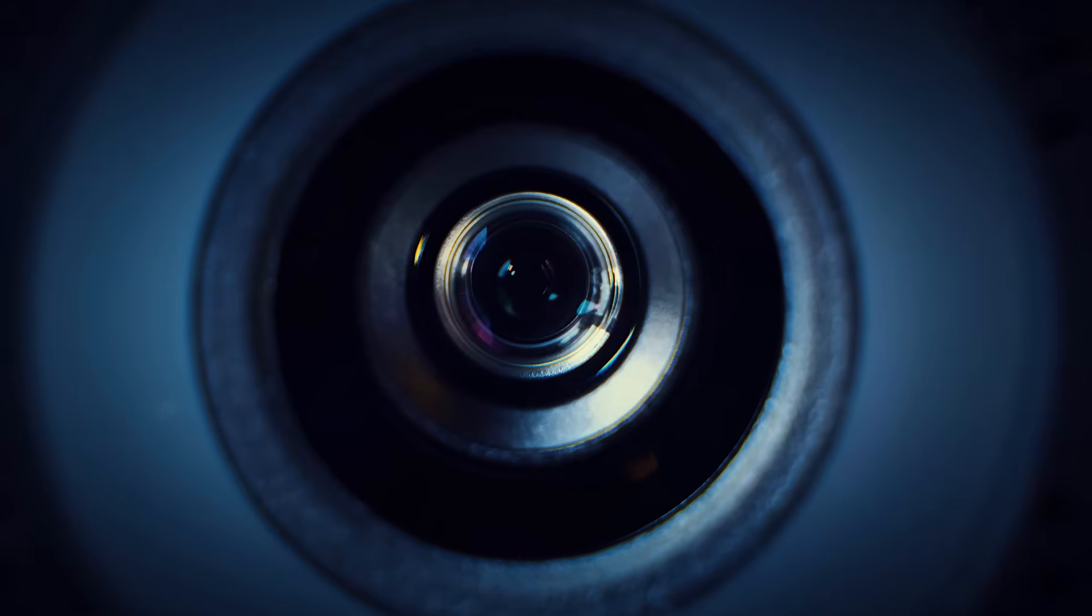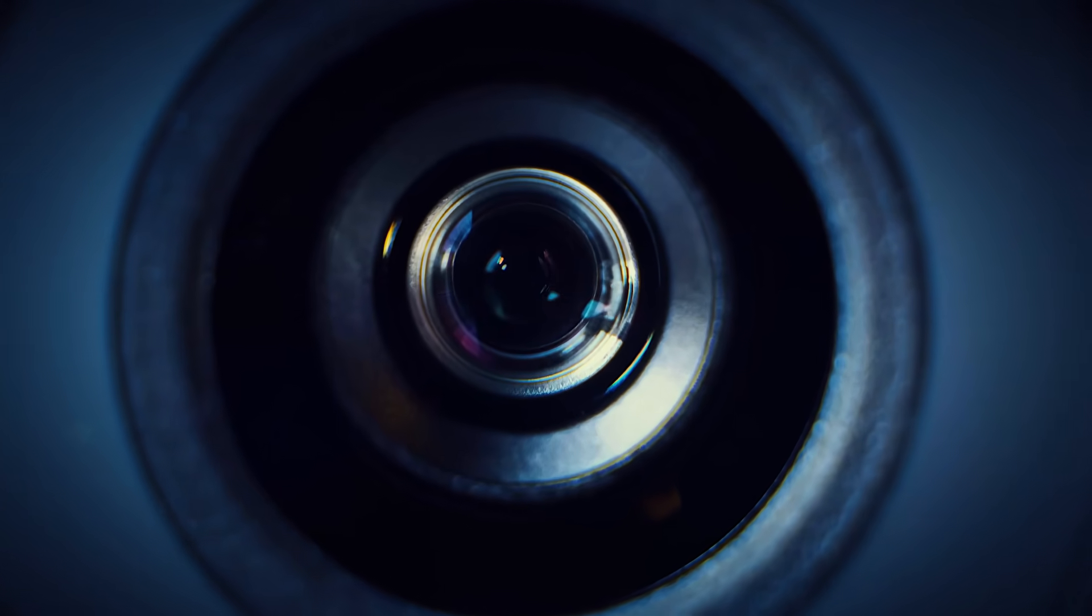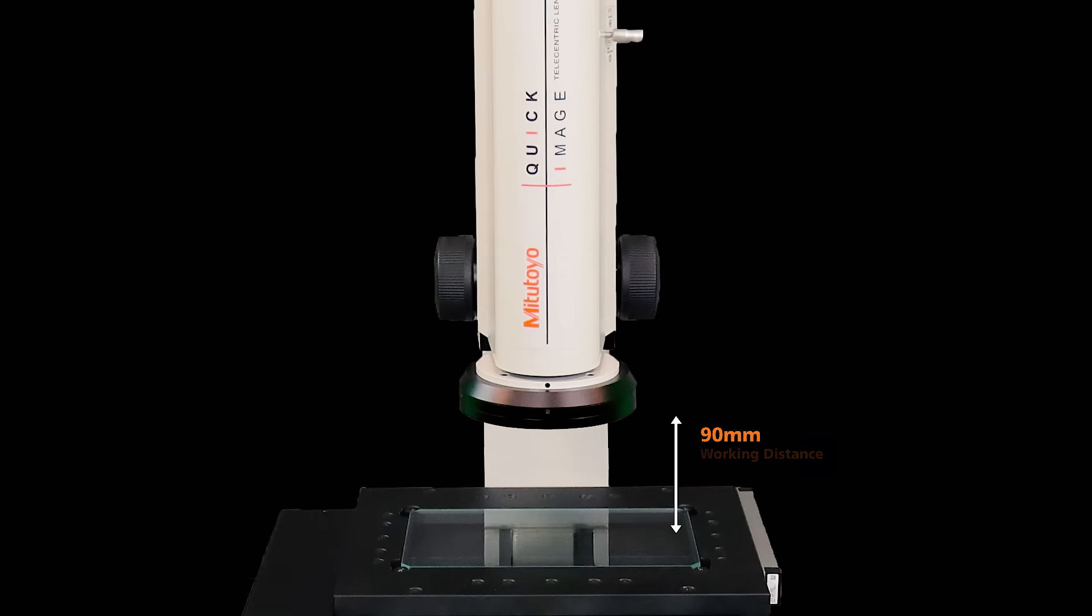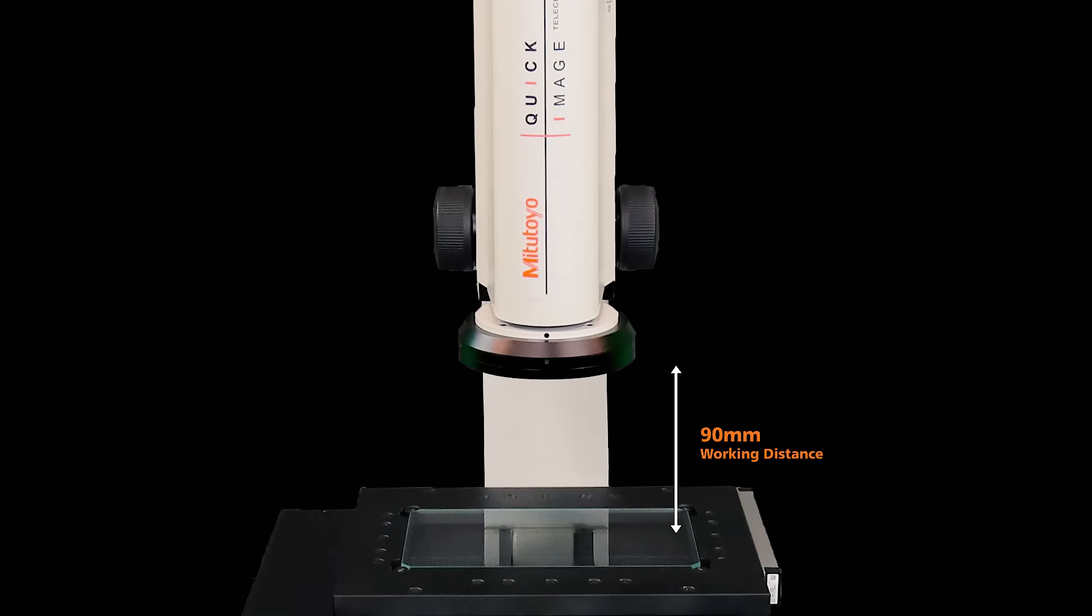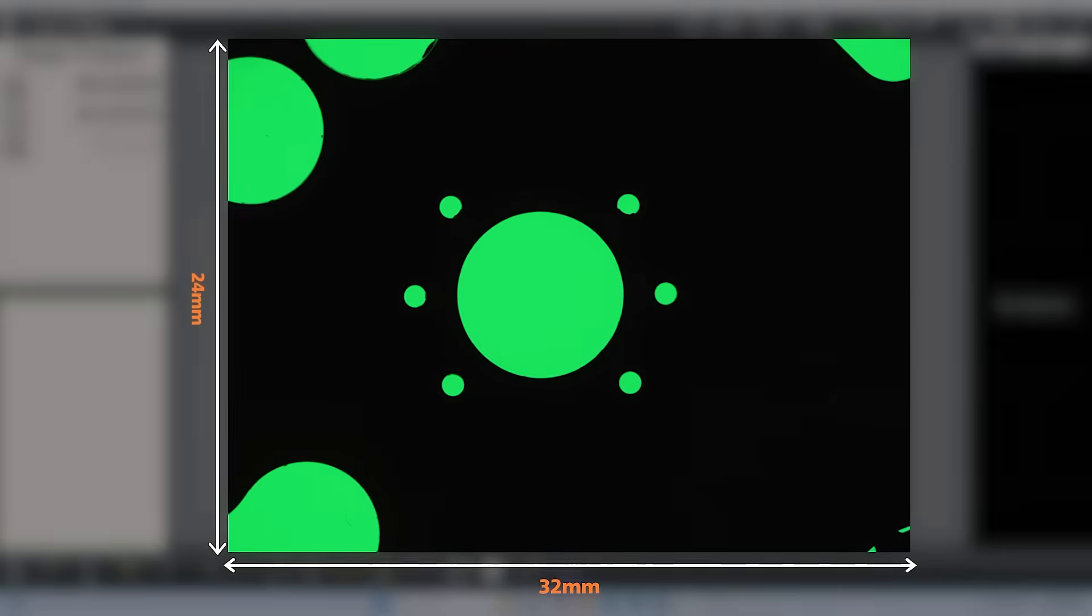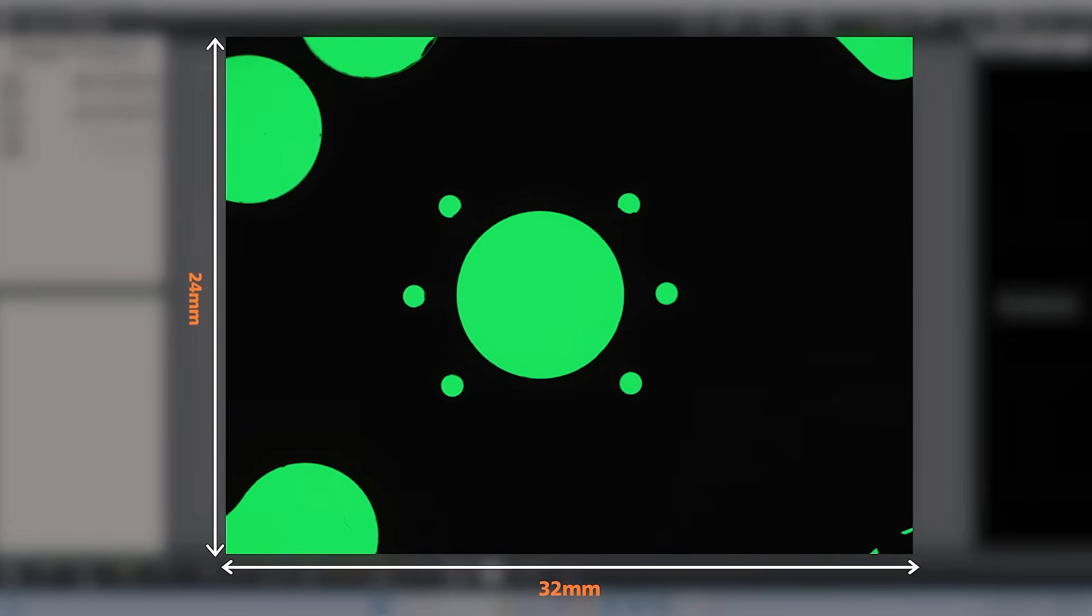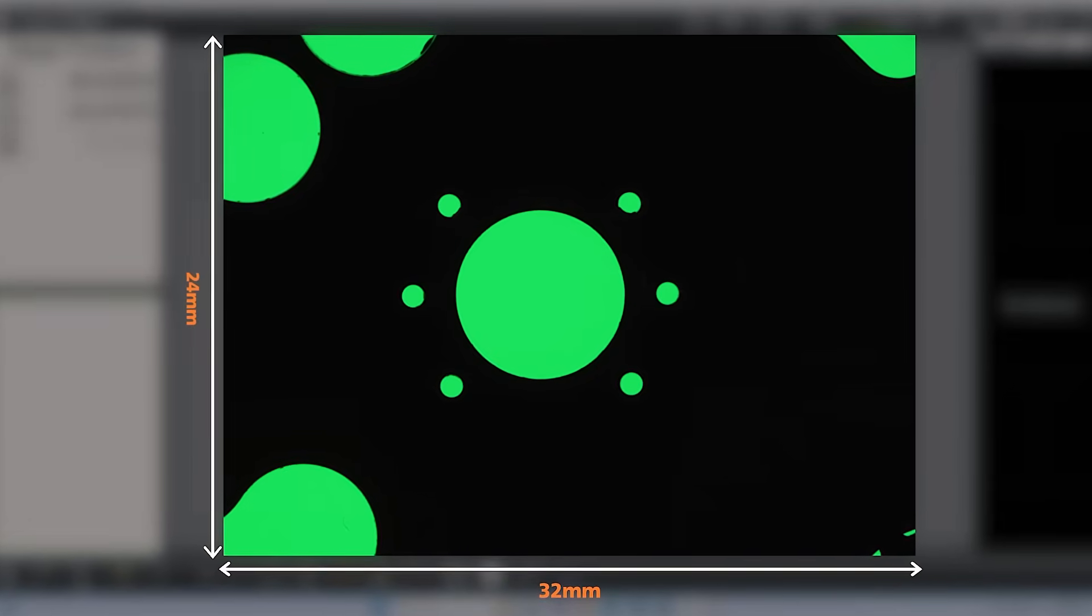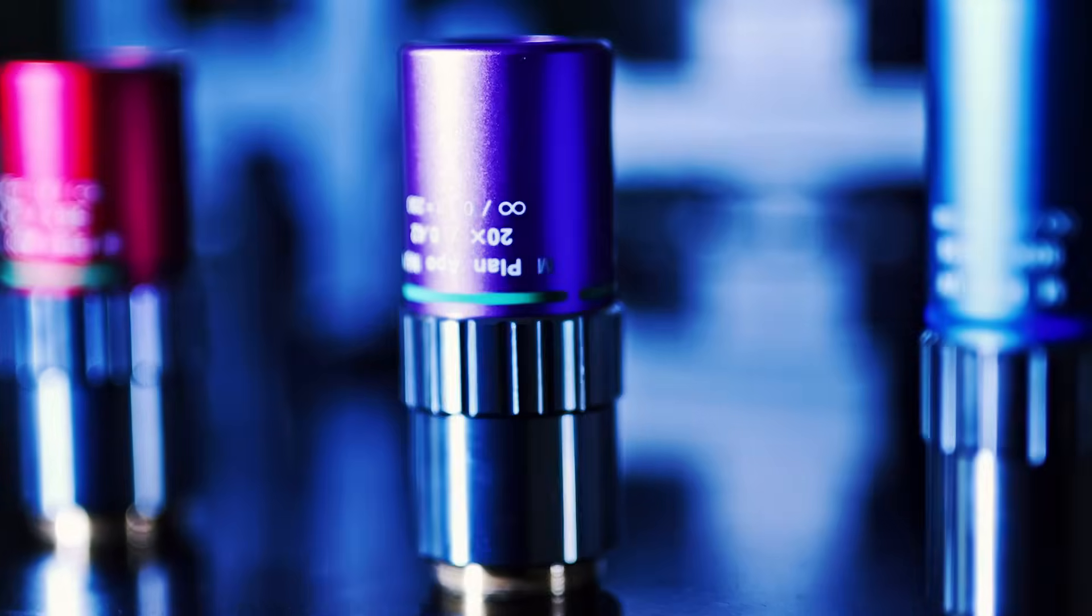A 90 millimeter working distance handles taller components. A 32 by 24 millimeter field of view captures significant detail in one frame. Combined with high-quality optics from Mitutoyo, the result is sharp, reliable measurement even on complex geometries or fine threads.